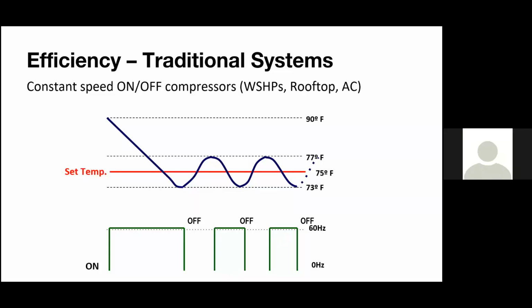And then something else to think about is that this on-off is bringing a lot of current to these compressors, which actually does hurt the lifetime of a compressor and the durability altogether. But, more importantly, efficiency. These compressors are not efficient. This is not an efficient operation because we're not meeting set point and we're using full bore on-off in order to get cooling capacity to reach that 75 degrees, right?